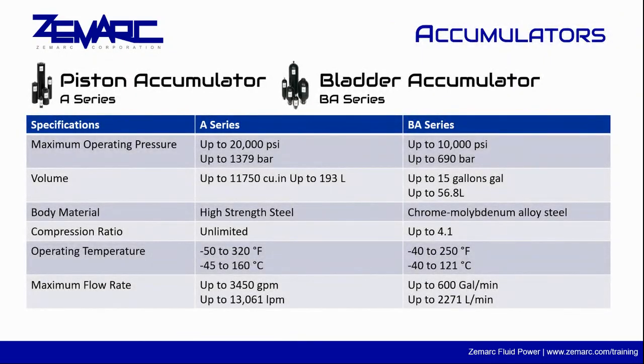Accumulators can be added into systems for many reasons, such as a backup system in case of a power loss, systems that require a low pressure for long periods with brief periods of high pressure, and to absorb shock loads.